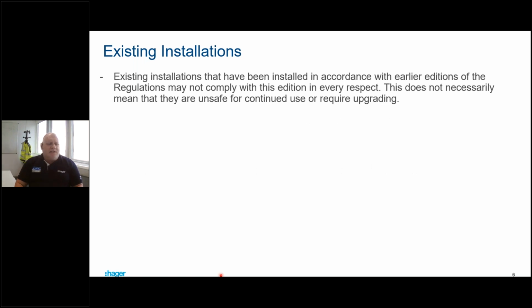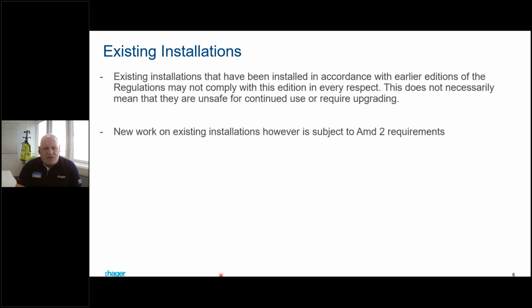So existing installations. So we all look at existing installations, we do EICRs, and as long as there's nothing wrong with those existing installations, we do not have to apply these regs retrospectively, okay? So we can leave them to run under a past amendment. Any new additions though, okay, must be to Amendment 2.